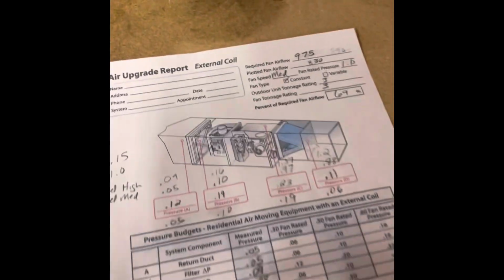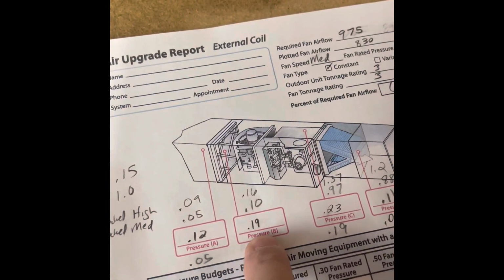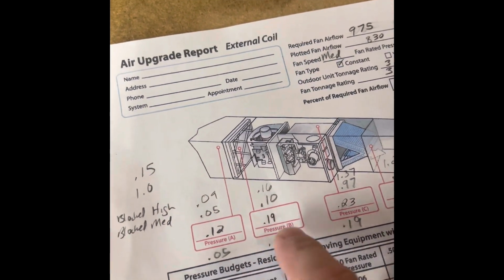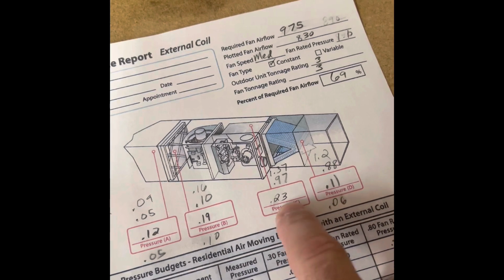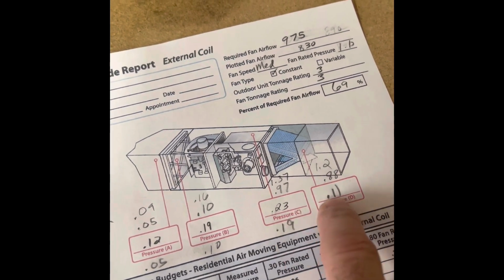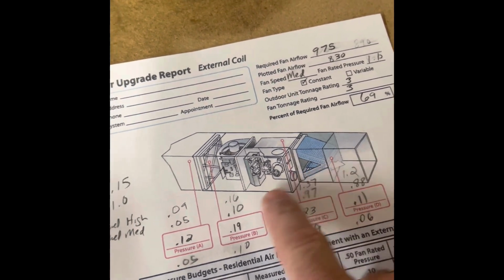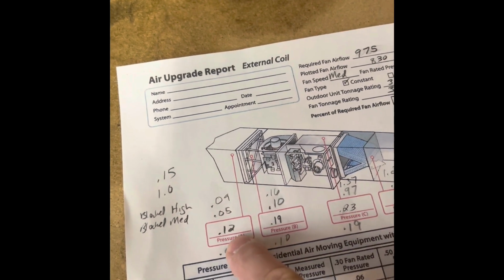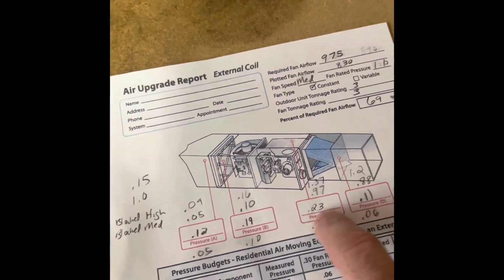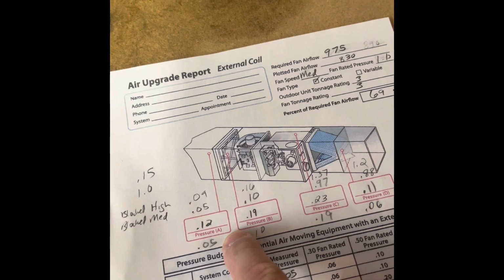So once we figured out the numbers there, we have a small pressure drop there, and a small pressure drop across the coil, so it tells me the coil's not dirty and my filter's not dirty. Really easily we can see what your system's doing.